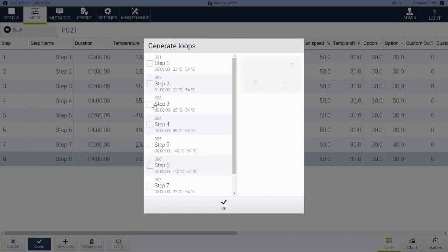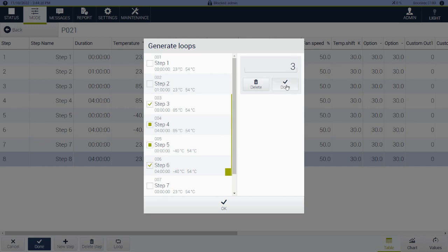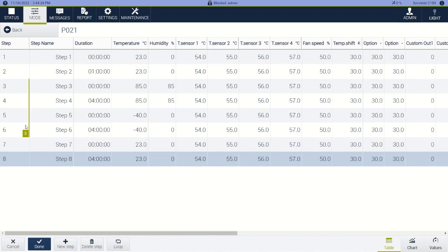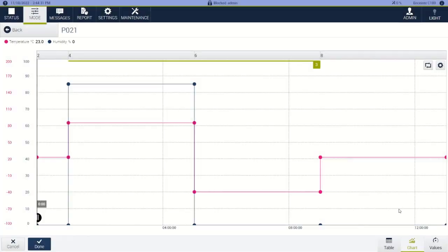But maybe we want to do multiple loops. So here we can select loop, and I want to loop these 85°C and minus 40°C set points and go through three times — so we get three transitions hot and cold. We'll hit done and then OK. And now you can see this loop bar appeared, so we're going to run through this three times. If we go back to the chart, you can see the loop areas — three sets of 85 and minus 40 for a more rigorous test.